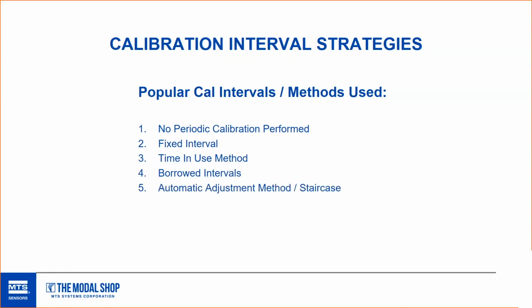An automatic adjustment method, or staircase. This one is basically each time a sensor is calibrated, the next cal interval is lengthened or shortened depending on the outcome, on the accuracy result of a sensor based on an arbitrary permissible error used. Similar to the time in use method, it can cause a challenging and staggered workload, but can be effective, and many companies use this approach.